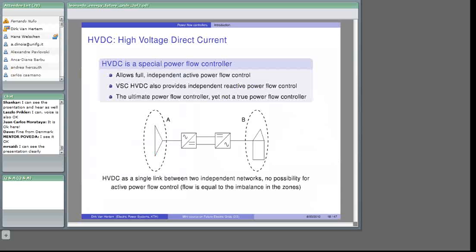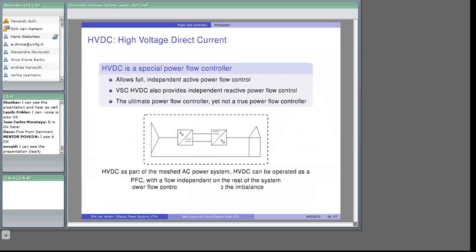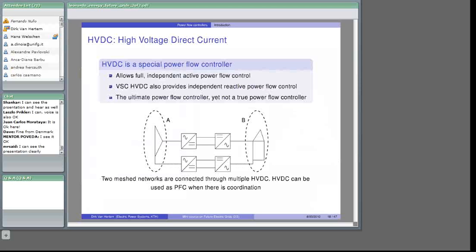If this would have been a phase shifter, the situation would be slightly different. If you have a parallel line, of course, you can have a full power flow control. Everything which is not going through the DC line will go to the AC line. So then it's what you would expect to happen with a normal power flow controlling device. And if you have two devices, or all the links between two systems are DC lines, then you do have a full coordination needed if you want to have power flow control, or even a stable operation.